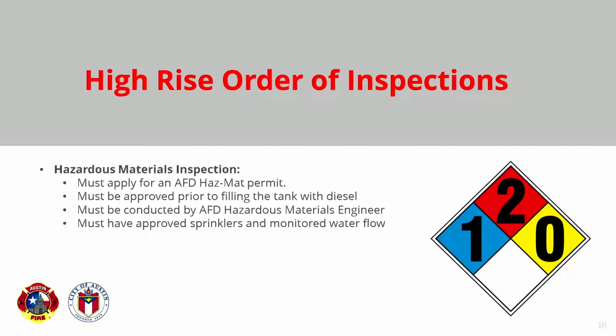In addition to being inspected by a hazmat engineer, you're going to have sprinklers in the area of the generator and the floor above and floor below, depending on the situation, but at least the generator area and the floor above. And it's going to have to be monitored off-site for water flow. That means if over the weekend your diesel catches fire and you have a water flow, the off-site monitoring is going to notify the general contractor and AFD or 911, and 911 is going to send a fire engine as a result of that water flow alarm.